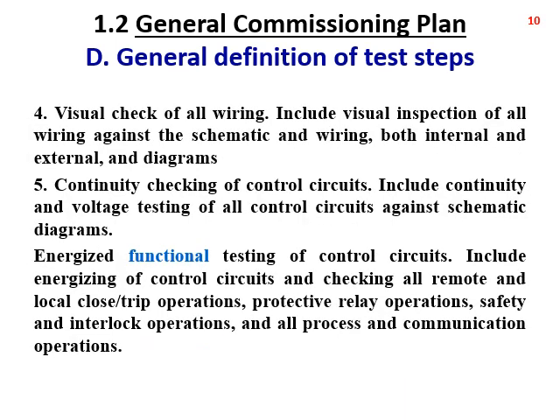General commissioning plan. D. General definition of test steps. Number 4. Visual check of all wiring. Include visual inspection of all wiring against the schematic and wiring, both internal and external, and diagrams. Number 5. Continuity checking of control circuits. Include continuity and voltage testing of all control circuits against the schematic diagram. Number 6. Energized functional testing of control circuits. Include energizing of control circuits and checking all remote and local close trip operations, protective relay operations, safety and interlock operations, and all process and communication operations.